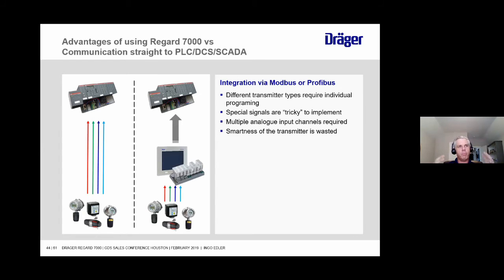And that's basically who we're competing with for the Regard 7000. We're competing with a customer who wants to take all these signals back to their DCS, or take them to a safety PLC or another type of PLC. Because basically the Regard 7000 is a PLC designed for gas detection, but it's so much easier to use because you can configure all those new inputs versus having to program them. And as far as the signal that goes from the Regard 7000 to their PLC or DCS, they would still be able to see all those values through the Modbus TCP/IP output, but they'd be read-only, and any changing of the information needs to happen at the Regard 7000.